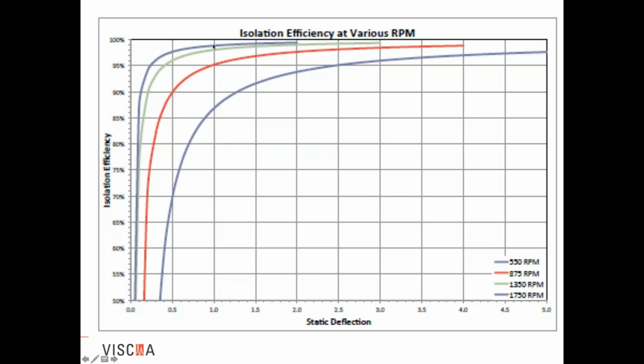And especially if I have a piece of equipment with 4 springs underneath it, it's impossible to balance that equipment so that each spring is at its rated load. So you'll typically get minus, you don't want to go plus because you're overloading the spring over its rated load, but you can be within 25% on the downside and not have any significant or any perceptible change in isolation efficiency. These other ones, at the lower RPMs, we'd be selecting a 3 or a 4-inch deflection spring at 550 RPMs, and it has the same issue. Within a range, there is no sensitivity to the isolation efficiency.